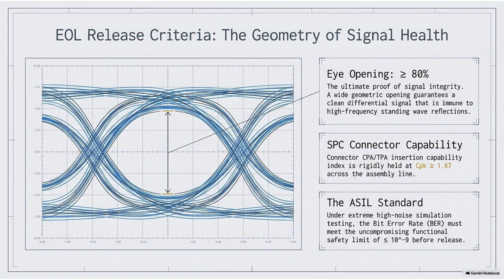But the babbling idiot test is the real star of the software validation. It tests the absolute worst-case scenario on the CAN network: flooding the bus with 95% high-priority junk data. In a CAN network, messages are prioritized by ID number — the lower the ID, the higher the priority. ID 0x000 and 0x001 have the absolute right-of-way; every other computer must stop talking and listen when a message with that ID is sent.